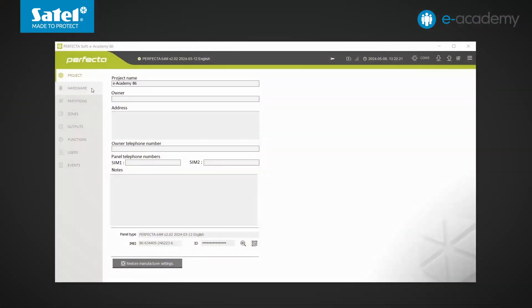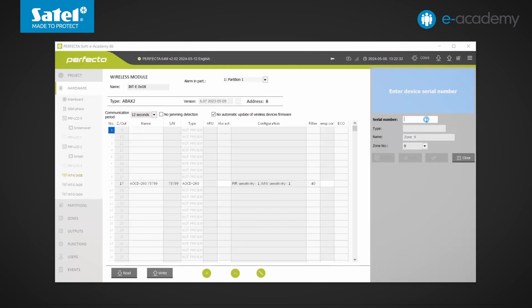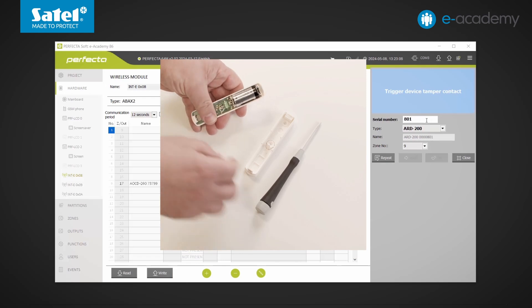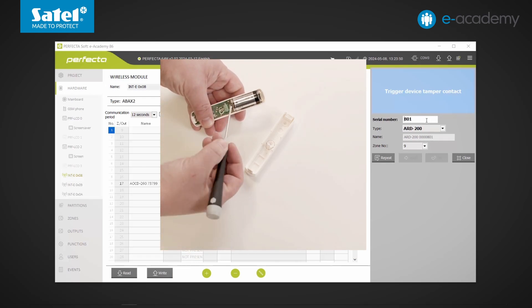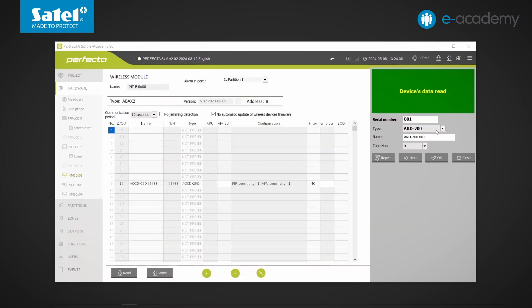I go over to PerfectaSoft and select the Hardware tab and the Wireless module. Now we'll add the ARD-200 to the system. I click the plus button and enter the serial number of the device. We add our detector in the first available position, specifying zone number 9. I put the battery into the detector and trigger the device tamper contact according to the instructions. The device data has been loaded and the detector will resume the mode in which it was operating.